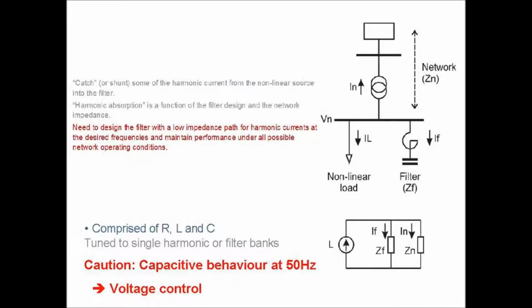The other thing then is shunt capacitive filters, or shunt passive filters. The idea of that is to shunt your harmonic current into the ground or away from the network in general.